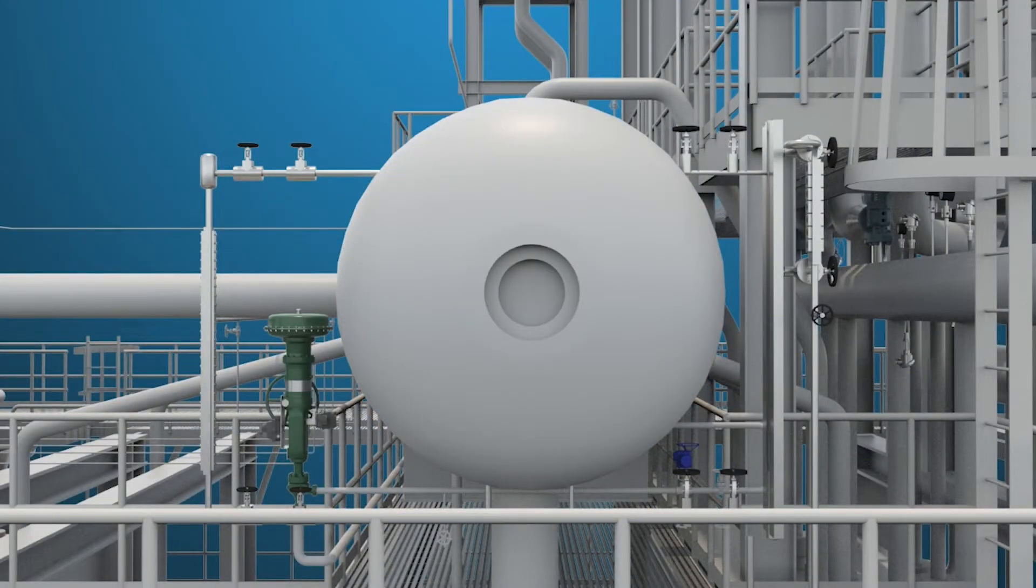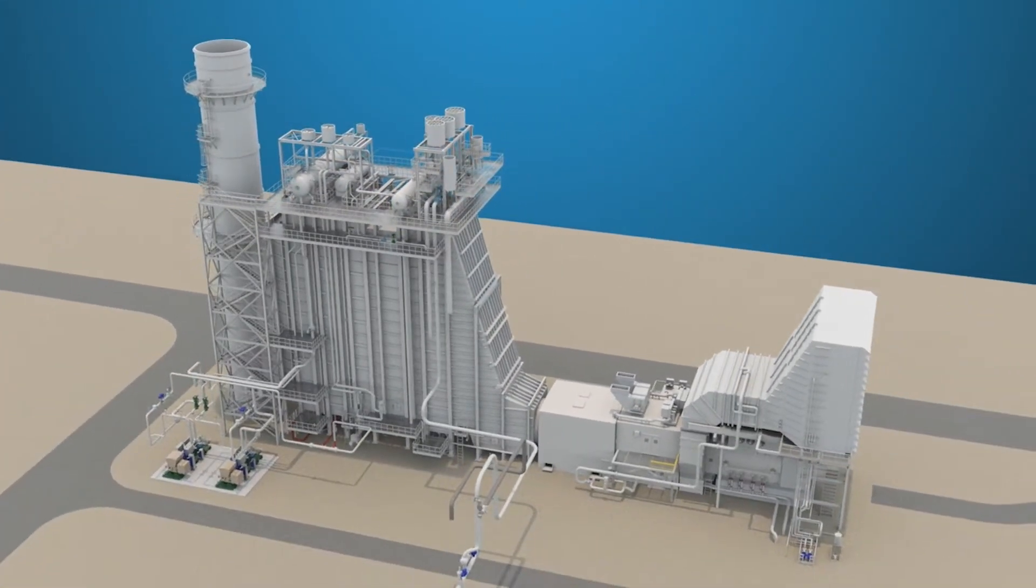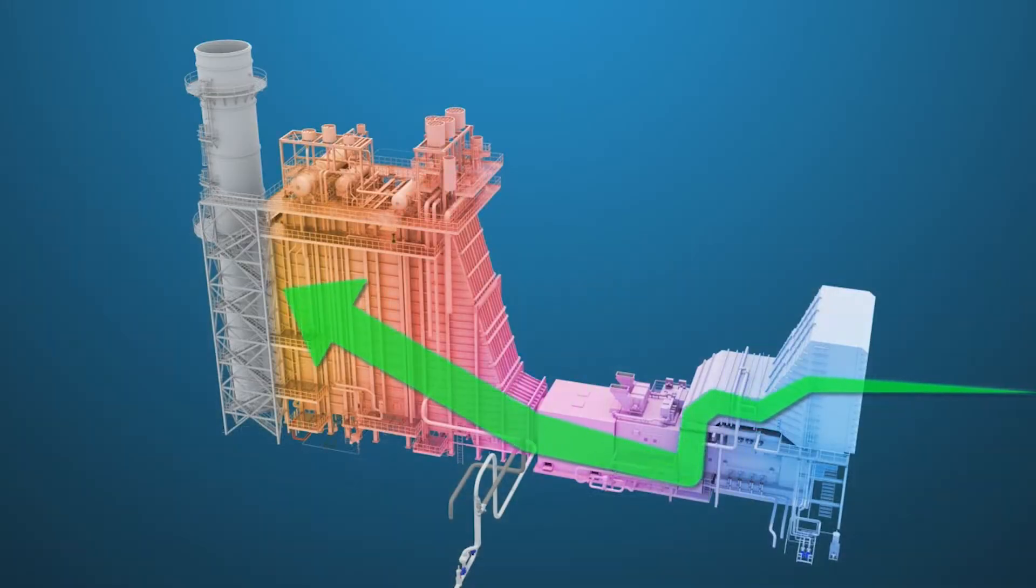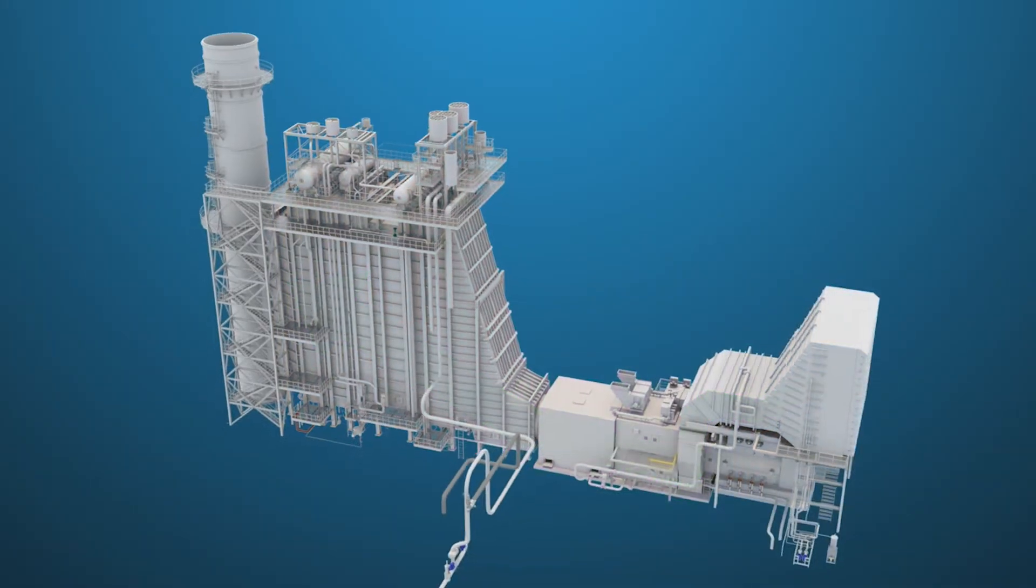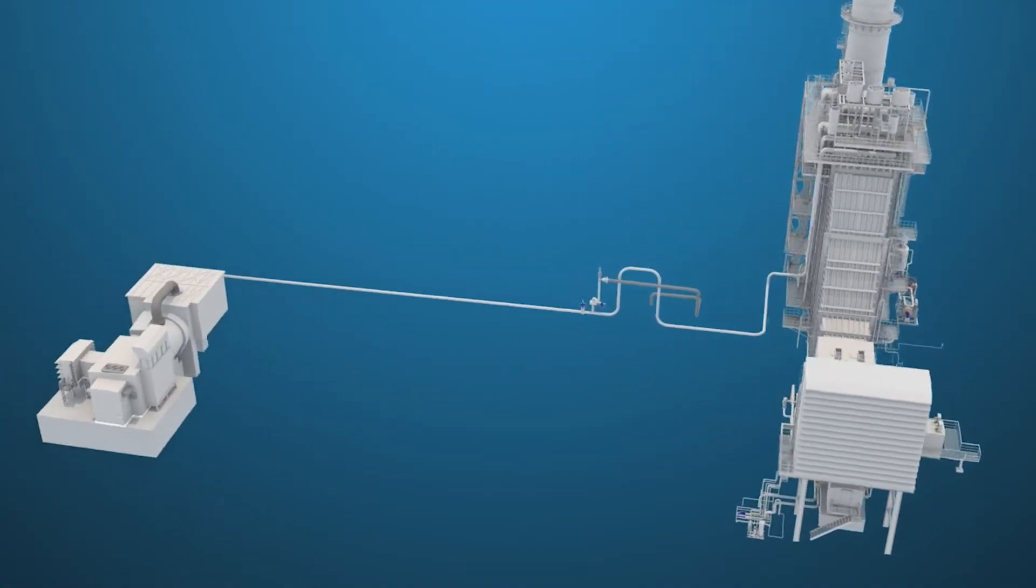Once proper drum level is attained, the vents are closed, combustion turbine started, and pressure and temperature will start to build in the HRSG. The turbine bypass system will be placed into operation and feed water flow will start to increase.